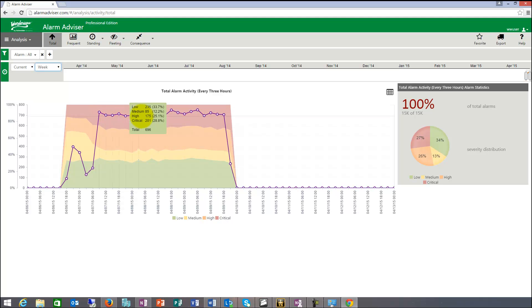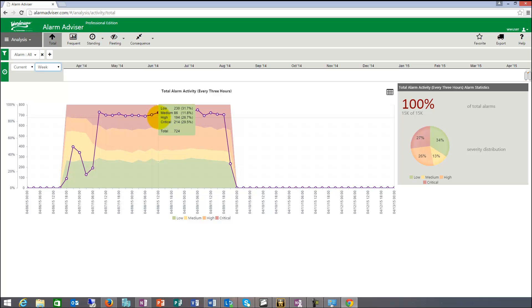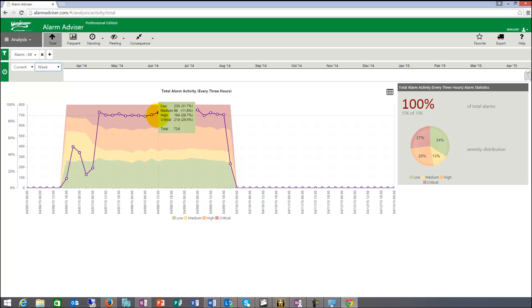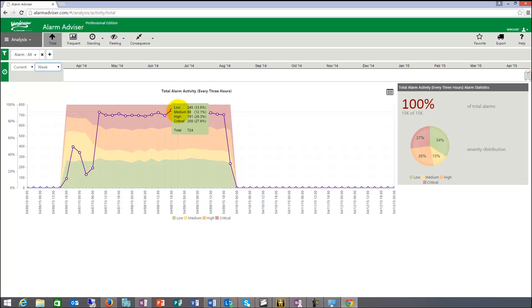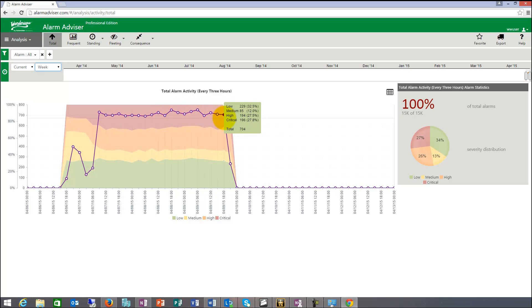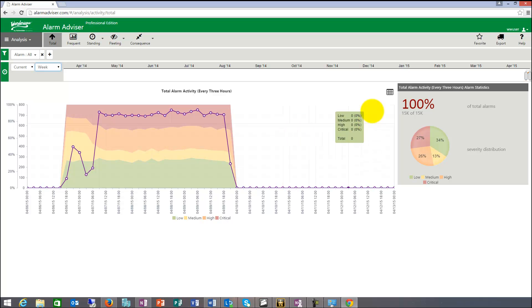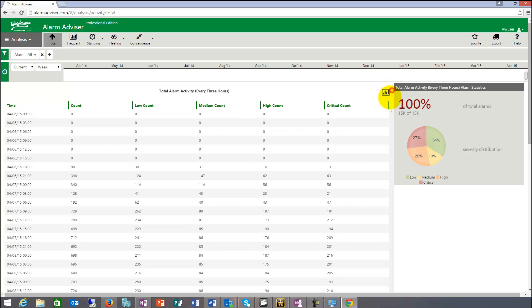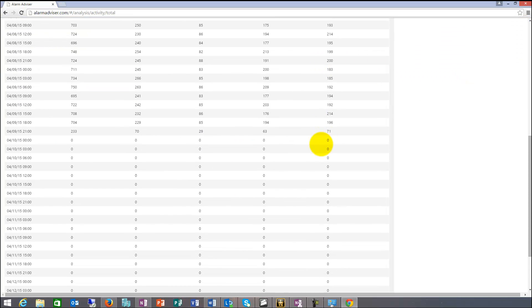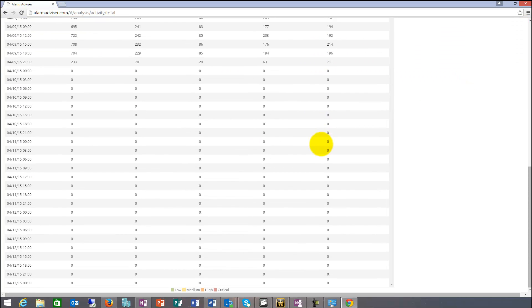So here I can see the total alarm counts, which are 724. And of those were 230 low, 86 medium, 194 high, and 214 critical. In a real plant, this would be bad because that would probably mean that my plant shuts down every five minutes.